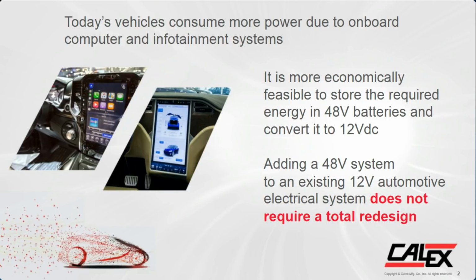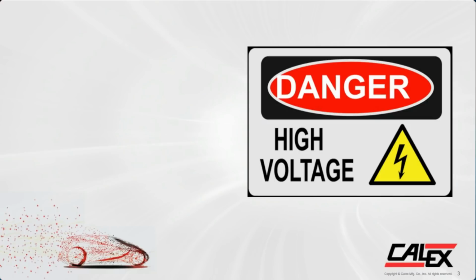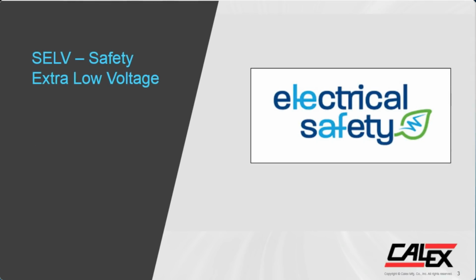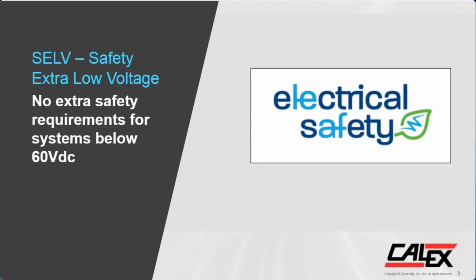A couple fundamentals for going to the 48. I'd like to cover SELV limits and a quick summary on lithium ion batteries. So when I reference SELV, as you can see from the slide, when you're doing SELV voltages, you're staying away from high voltage requirements and safety requirements. SELV stands for safety extra low voltage. This comes from UL 60950-1, and that states that an SELV circuit is a secondary circuit which is so designed and protected that under normal and single fault conditions, its voltages do not exceed a safe value.